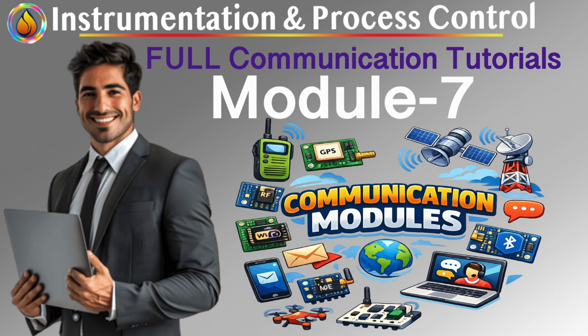The operator interface: from controller to window. This is one of the most subtle but important shifts. In Foundation Fieldbus, the operator interface is no longer the brain. It becomes a window into distributed control logic, with function blocks executing in the field, and process values and diagnostics flowing across the bus. The tutorial makes this explicit: the operator interface displays data and transfers high-level control information, like set points, but does not necessarily execute the control itself. This means losing the HMI doesn't kill the control loop, and doesn't necessarily stop the process. Control becomes physically closer to the process. That proximity matters for stability, latency, and resilience.